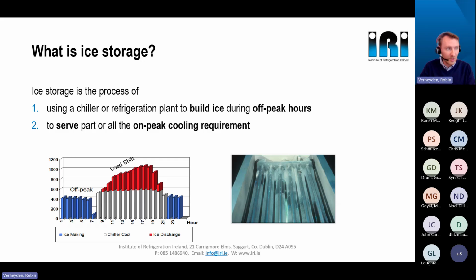That brings us to the definition: ice thermal storage is a process of using a chiller or refrigeration plant to build ice during off-peak hours, and to serve part or all of the on-peak cooling requirements, as shown in the graph. The blue indicates off-peak ice making, while the red indicates the period in an HVAC profile, for example, where you discharge the ice — using it to reduce the chiller size.